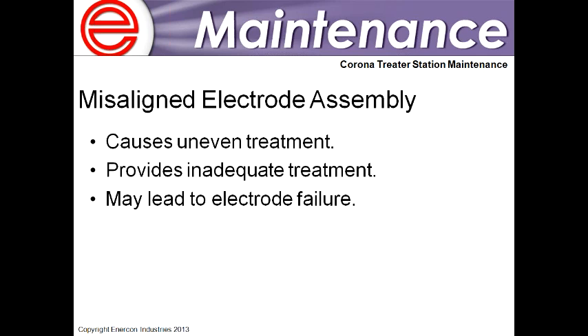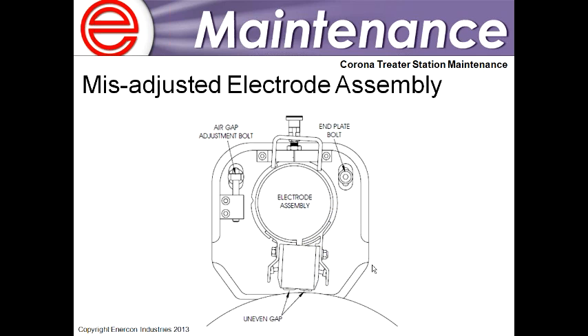So if you can go back to that slide, Mark, where we show the misadjusted electrode. Yeah. In this particular picture, the electrode on the right of that assembly is going to get more power than the electrode on the left side of the assembly. So if you have 5 kilowatts being dissipated on this electrode, and let's say they're both uniformly gapped, each would get 2,500 watts. When they're misaligned, one's going to see more than 2,500 watts than the other, because the distance between that electrode and the ground is a lot shorter. So in addition to Matt's recent comment about poor treatment results, which are certainly also part of this, that electrode, if you leave it like this, will likely overheat, and the overheating will cause a crack, and the crack will cause the treater to shut off. And so it's important that the electrode air gap is adjusted properly both up and down and side to side.